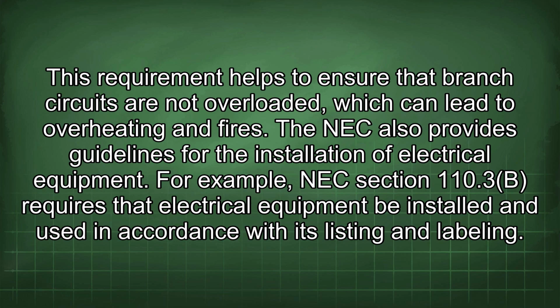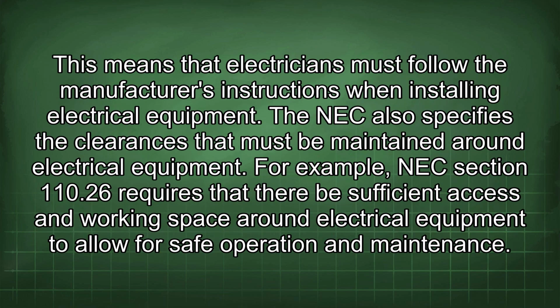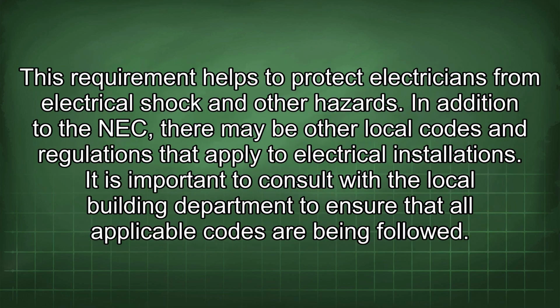The NEC also provides guidelines for the installation of electrical equipment. For example, NEC section 110.3(B) requires that electrical equipment be installed and used in accordance with its listing and labeling. This means that electricians must follow the manufacturer's instructions when installing electrical equipment. The NEC also specifies the clearances that must be maintained around electrical equipment. For example, NEC section 110.26 requires that there be sufficient access and working space around electrical equipment to allow for safe operation and maintenance. This requirement helps to protect electricians from electrical shock and other hazards.